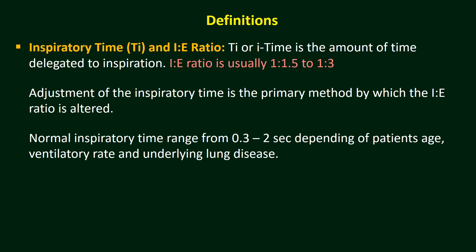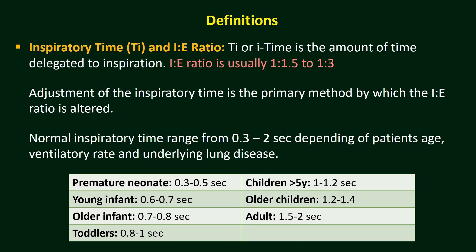Adjustment of Inspiratory Time is the primary method by which the Inspiratory-Expiratory Ratio is set. When we set respiratory rate and Inspiratory Time, the I:E Ratio is set automatically. On the other hand, when we set rate and I:E Ratio, Inspiratory Time automatically gets set. Normal Inspiratory Time ranges from 0.3 to 2 seconds depending on patient's age, ventilatory rate, and underlying lung conditions. There is no hard and fast rule, but this can be an initial setup.